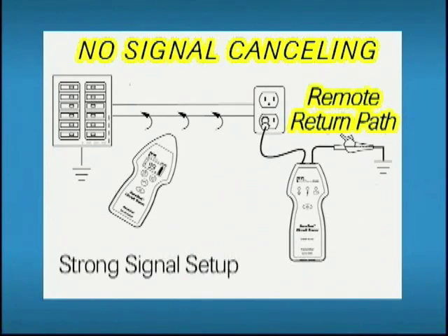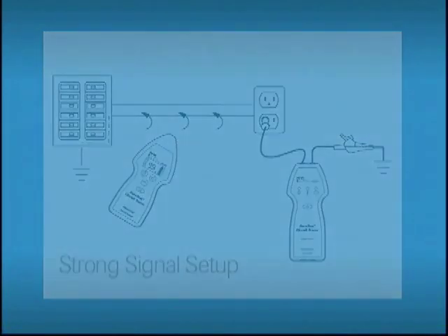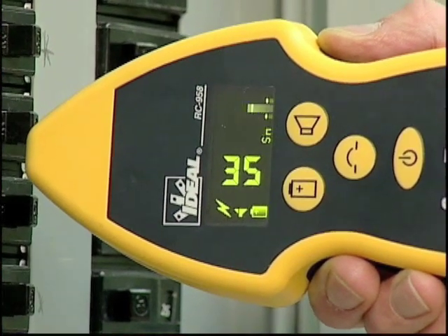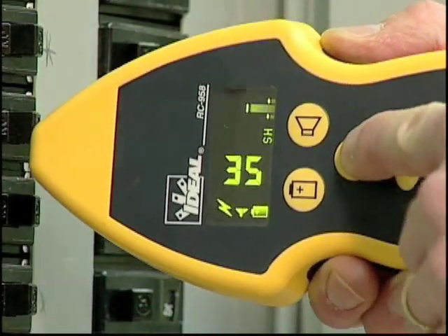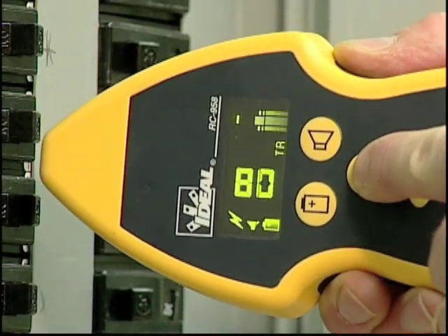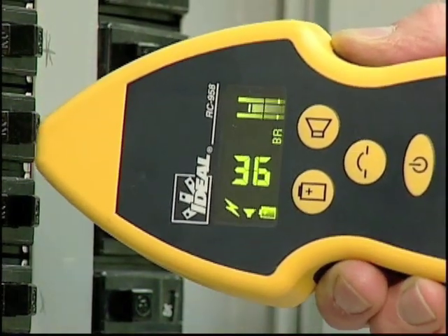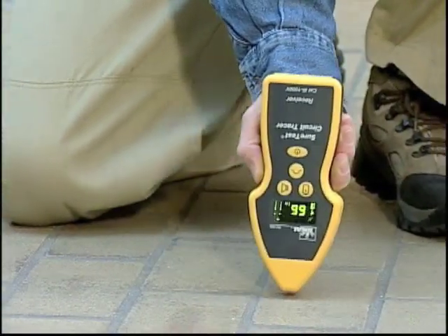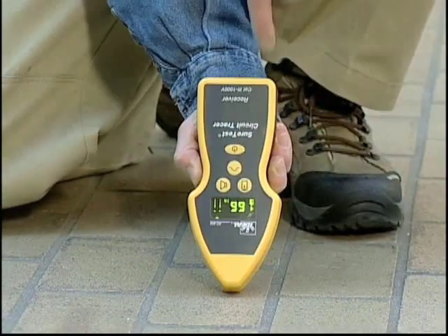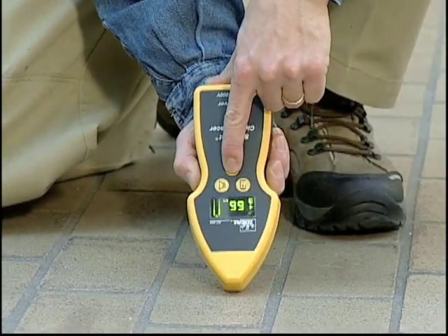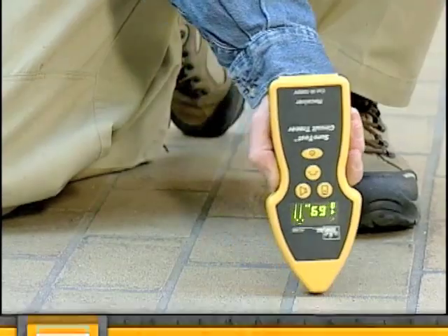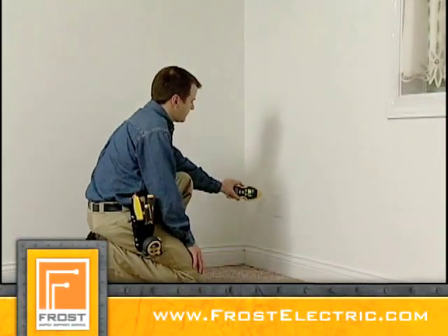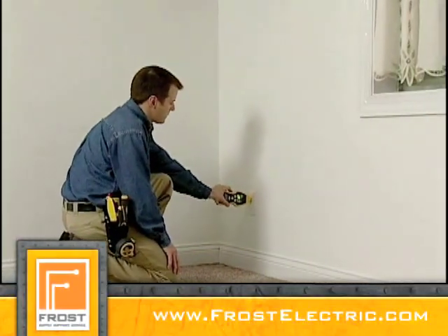Sure Test receivers offer four modes of sensitivity. In general, you should always start at the maximum setting until the receiver finds the circuit under test, then reduce the sensitivity mode if the meter pegs at 99 continuously. The indication of the received signal depends on how the receiver is pointed in relation to the source of the signal.